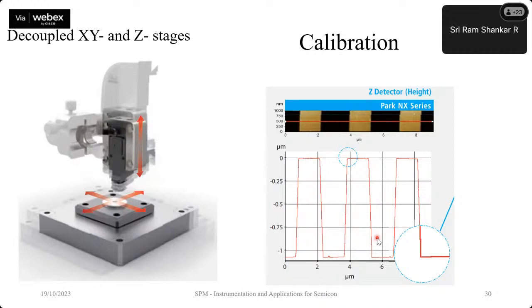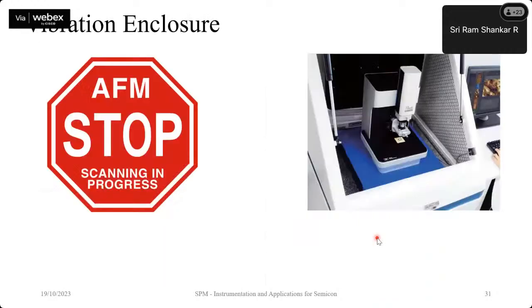This calibration is very important and needs to be performed every week or every now and then in AFM instruments. It's also very important that this AFM system is enclosed within a vibration isolated enclosure. Firstly, you'll be housing this entire system on a platform that is isolated from the ground through a pneumatic column or air column that also acts as vibration isolation, and it's also housed within a certain chamber that provides acoustic isolation.